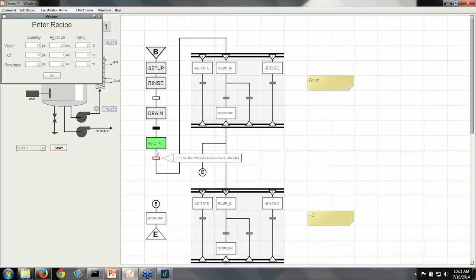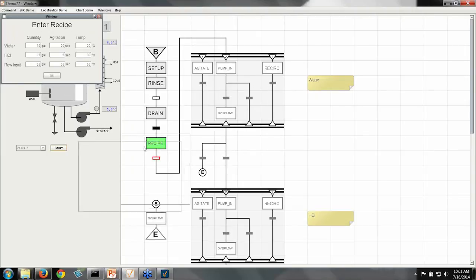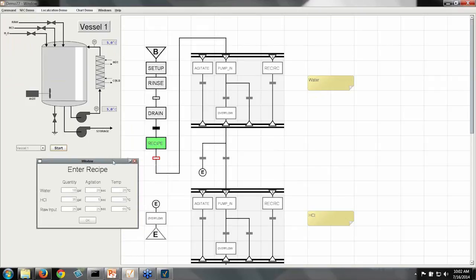And then as soon as it's done that, it's going to ask me for a recipe. Now it's important to realize here that the sequential function charts always execute on the gateway. They don't actually execute on the client, even though the client can monitor their progress. But there's a bunch of mechanisms included that help you communicate to and from a client. So in this case, because this client, the one I'm using right now, is the one who started the batch, the chart is asking me, the operator, for the recipe.